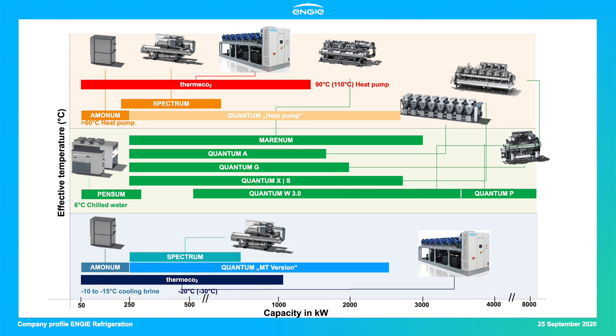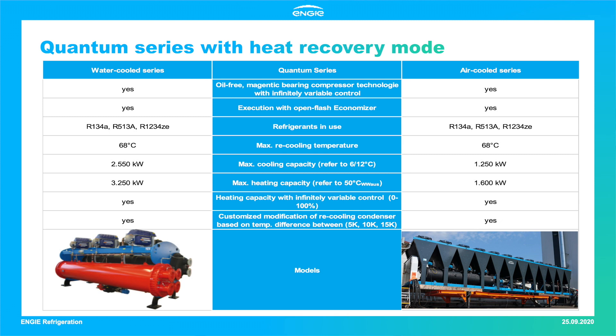Each series contains both heat pumps and chilled water units. An Engie option enabling the usage of waste heat from chilled water units is the heat recovery mode. This option is available for Quantum models — air-cooled and water-cooled chillers — working with the oil-free magnetic bearing concept provided by Danfoss Turbocor. All Quantum models are executed with open-flash economizers and are available for the A1-classified refrigerants R134A and R513A, as well as the low-GWP refrigerant R1234ze.